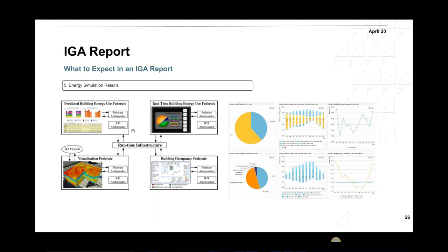And I would simulate the building, get the results, and then compare them to the utility bills for that year, for the baseline. And then if I am within 30% per month and 15% per year, that would be enough. Normally it's 15% per month as per ASHRAE Guideline 14. And then compare that also on an annual level, which should be around 15%. So that will give you comfort that you have done it properly.